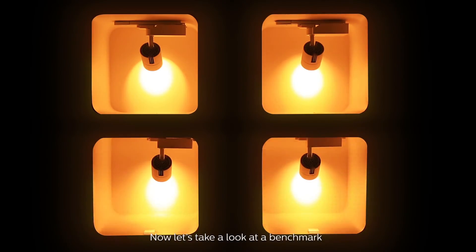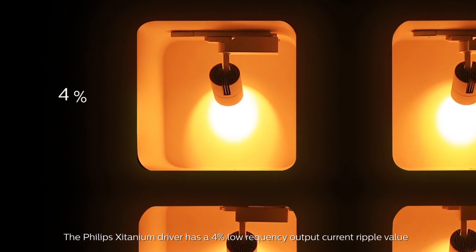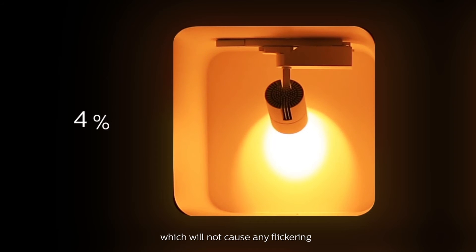Now let's take a look at a benchmark. Here we present four spotlights which use the same LED module but different drivers with different low ripple currents at 4%, 10%, 20%, and 30%. It's very obvious that the lower the output current ripple, the lower the flickering phenomenon. The Philips Xitanium driver has a 4% low frequency output current ripple value, which will not cause any flickering.